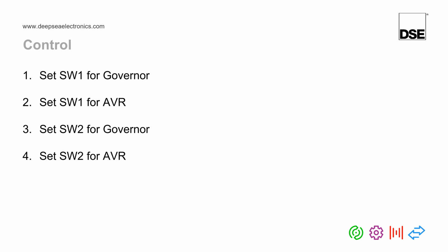We need to make sure that we always do the governor first when doing the switch 1 and switch 2 setup procedure. The reason is that generator frequency can affect voltage, however generator voltage does not affect frequency. So in the procedure you'll see I always start with switch 1 for the governor first, or switch 2 for the governor first. We'll go through how we set switch 1 for the governor and AVR first, and then on to how we set switch 2 for the governor and AVR.